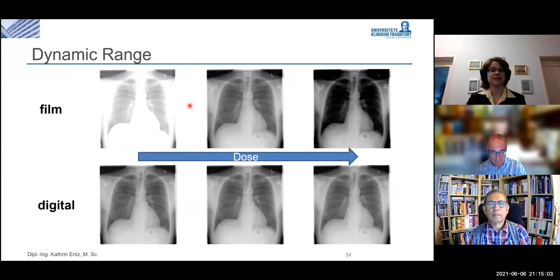When you move to the digital world and use a digital detector, it is not that straightforward anymore. So again, you have here your ideal image. And if you're using not enough dose, then of course, at some point you have too much noise in your image and you will see that the image is not perfect and there's something wrong. But on the other hand here, it is much more difficult because you don't really see that you're using too much dose.